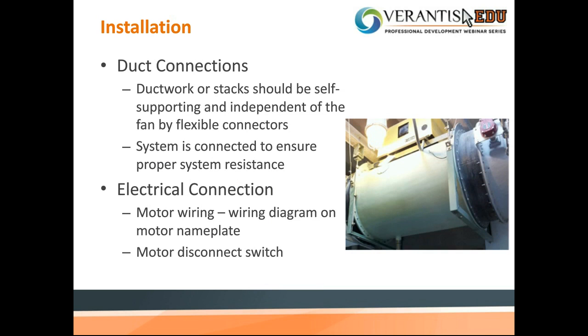So, installation with duct connections. Ductwork or stacks should be self-supporting and independent of the fan by a flexible connector. We have had it where a stub stack is placed on top of a fan, but the fan housing and base are not designed to support that weight. Typically, a fan is not designed to support the weight of the ductwork. So that's why you put flex connectors in there. So if there's an issue with the ductwork, the fan is operating freely of what happens with the duct. So definitely put flex connectors on the inlet and the outlet of the fan to ensure proper system resistance.